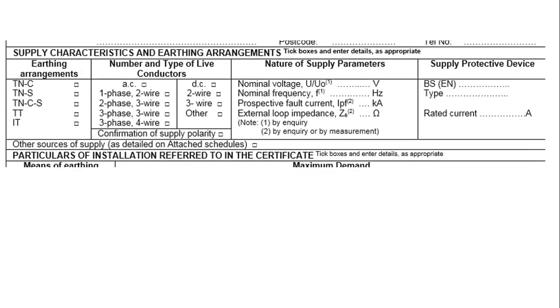So now we can write that on our electrical installation certificate. Either on page one or page two, you will see supply characteristics and earthing arrangements, and here we have ZE. In this box, we need to put the value — we've just got the value of 0.50 ohms. We can drop the zero and put 0.5 in that box.